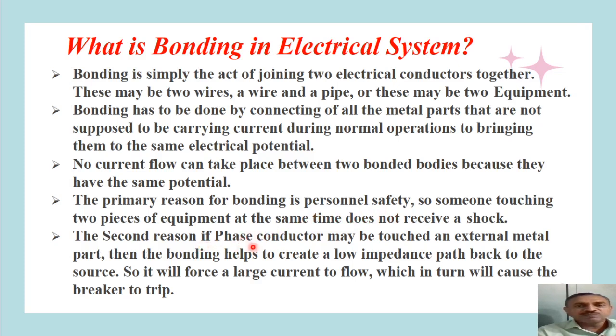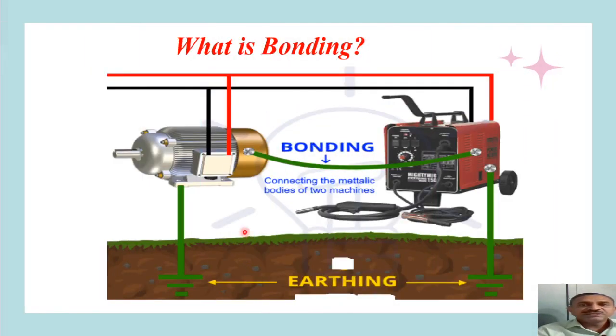The second reason of making bonding is that if phase conductor of one of equipment has touched the external metallic part, then the bonding will help to create a low impedance path back to the source. Thereby the current that is flowing through this mechanism of circuit will be detected by the breaker. Breaker will trip and both the equipment will be switched off, and further loss of any equipment or the person will be avoided. Now what is bonding is clear in this picture.